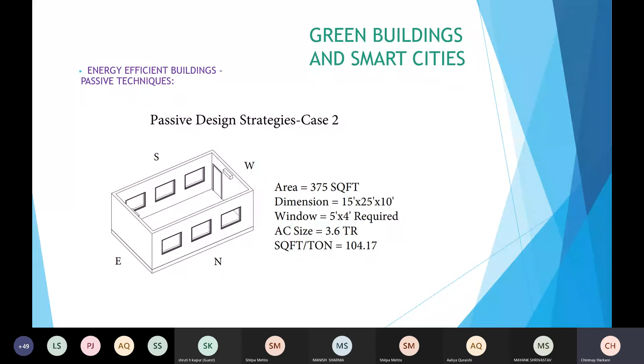This is the exact same room - you can see no difference. Both are oriented east to west, both have the same size windows, same size room walls. This requires 3.6 TR of air conditioning, and here you need only a 1 TR AC. You've reduced the size of your AC by almost 75%, just by using good quality glass and insulating your walls and roof. Take a moment to think about what has happened.